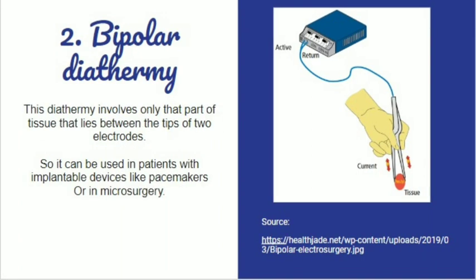Bipolar diathermy involves only that part of the tissue that lies between the tips of the two electrodes, because energy goes from the generator to one electrode, through that tissue, and then to the other electrode and back to the generator. So it can be used in patients with implantable devices like pacemakers, because current will not pass through the body. They are also used in microsurgery because they can target very small tissues that fit between those tweezers.